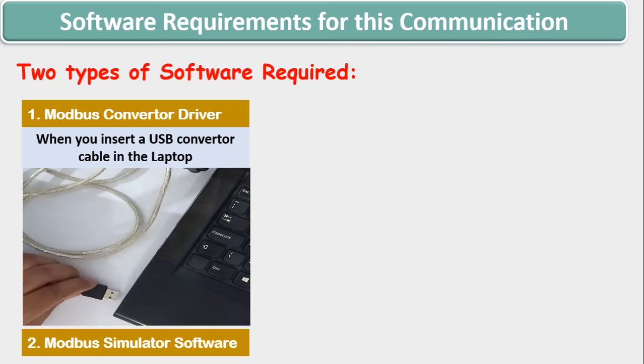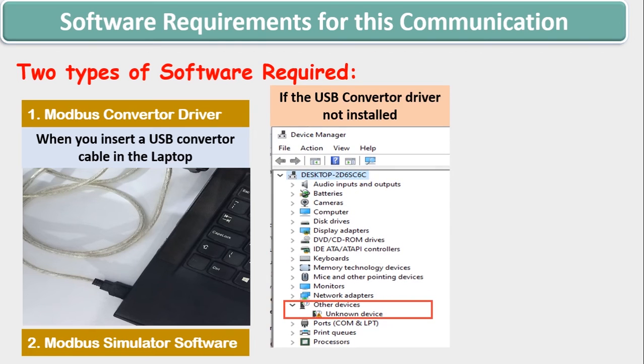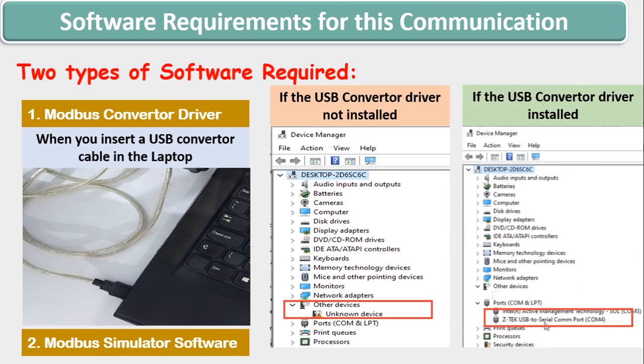Once the driver is installed, when you insert a Modbus RS-485 USB converter cable in the laptop port — if the USB converter driver was not installed or was installed incorrectly, it will give you an error of unknown device as highlighted in the device manager section of the computer. You can right-click on the unknown device and go to the option of update driver. You can update the driver by putting the driver CD in the CD-ROM or update it via online. If the RS-485 USB converter driver is installed correctly, you can see that a COM port number is assigned to your converter — in this case, COM port number 4 is given to your ZTEK USB to serial converter.